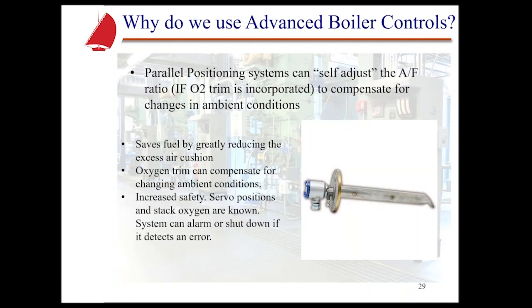So we talked about O2 trim briefly. By incorporating O2 trim, it's going to allow us to compensate for ambient condition changes. That's a big deal. This is the feedback or closed loop, if you will, to make sure that what we wanted for a particular air-fuel ratio, say when we set it up on one particular day, holds 6 months from now, as ambient conditions change. The O2 value is stored. Not only the positions that we told the servos to be in at that particular firing rate, but we are also saving what we want that O2 sensor value to be at that particular firing rate.